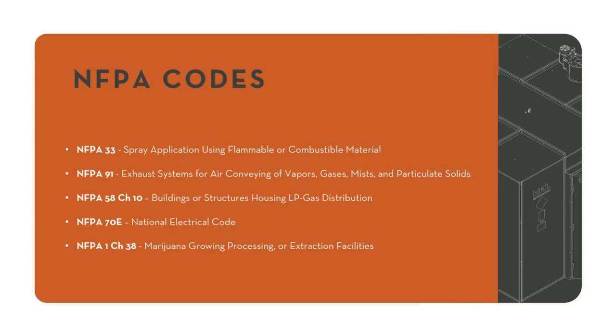And then I have NFPA 70, the National Electric Code, and that's where both of those definitions for C1D1 and C1D2 come from. And then NFPA 1, Chapter 38, is very interesting because it's the first cannabis-specific code in the National Fire Protection Code. It calls for a lot of different things, and I think it's interesting to look at these because they are very cannabis specific. They call for a lot of those interlocks I talked about earlier. They want the lights and the fans to be interlocked. They want ancillary components to be interlocked, like heaters and chillers, and they want the fire system to be interlocked as well.